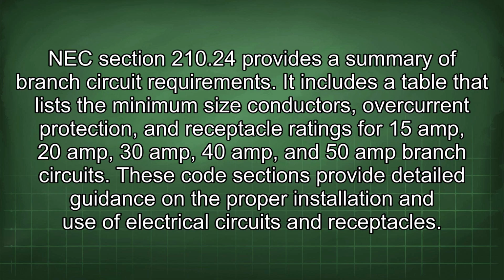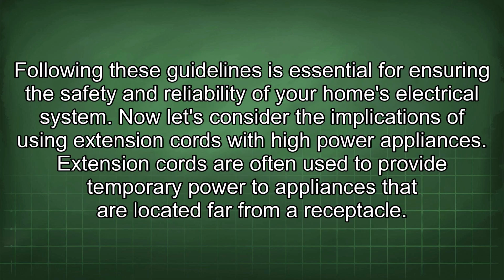NEC Section 210.24 provides a summary of branch circuit requirements. It includes a table that lists the minimum size conductors, overcurrent protection, and receptacle ratings for 15 amp, 20 amp, 30 amp, 40 amp, and 50 amp branch circuits. These code sections provide detailed guidance on the proper installation and use of electrical circuits and receptacles. Following these guidelines is essential for ensuring the safety and reliability of your home's electrical system.